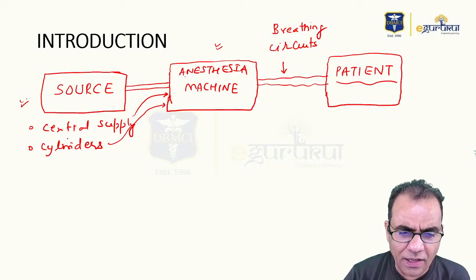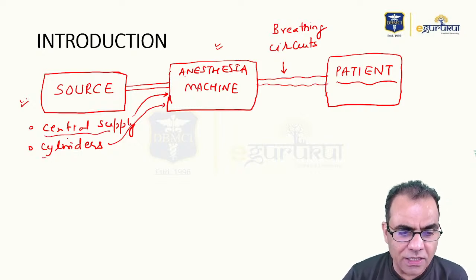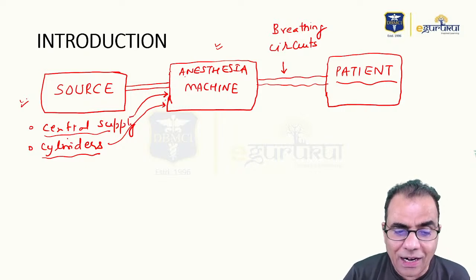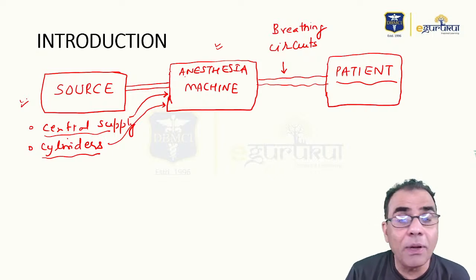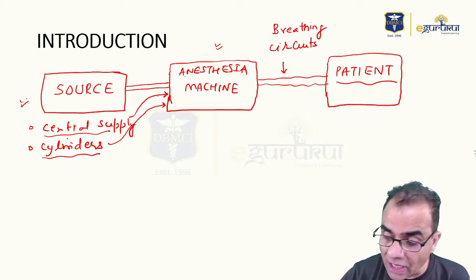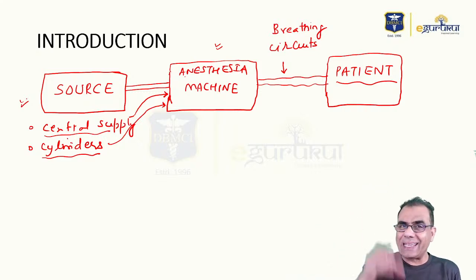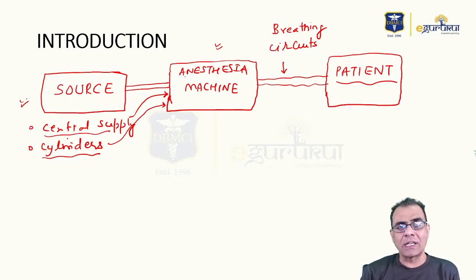Now, another very important thing is that the central supply or cylinders are being attached to the anesthesia machine. If they get attached wrongly, then it can be disastrous. Means by chance, if the nitrous oxide pipe gets attached to the oxygen pipe, or a nitrous oxide cylinder at the place of the oxygen cylinder, and the patient receives 100% nitrous oxide, the patient is definitely going to die. So there should be something which prevents the wrong fitting of the central supply pipelines and wrong fitting of cylinders to the anesthesia machine.